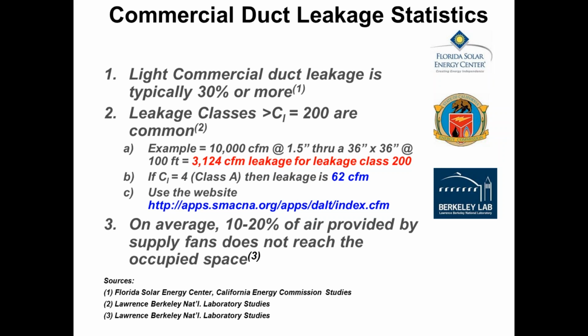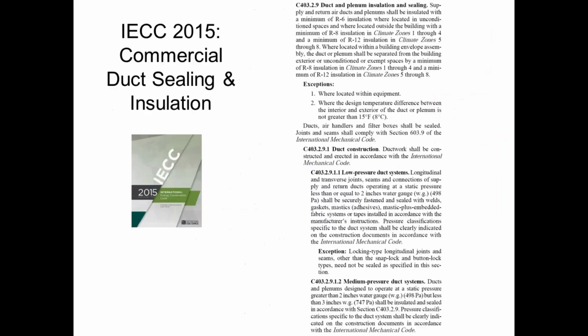On average, 10 to 20% of the air that goes through your supply fan never reaches the occupied space, right? 30% of it's leaking, but some of that leakage makes its way to the ceiling cavity into your space. The rest of it makes its way out the sidewalls or out the roof line or somewhere else, right? So it's a pretty big problem, and it's pretty easy to solve.